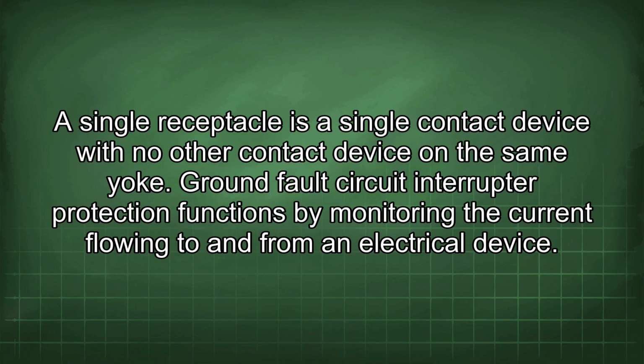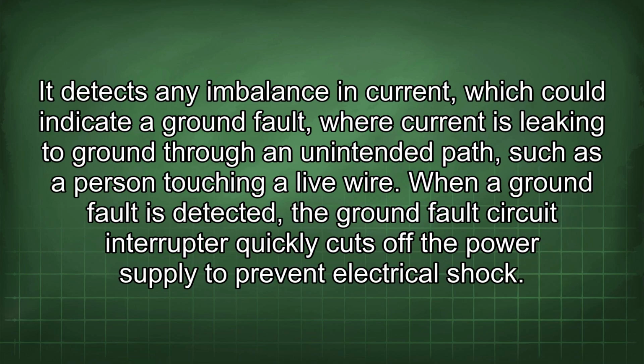Ground fault circuit interrupter protection functions by monitoring the current flowing to and from an electrical device. It detects any imbalance in current, which could indicate a ground fault, where current is leaking to ground through an unintended path, such as a person touching a live wire. When a ground fault is detected, the ground fault circuit interrupter quickly cuts off the power supply to prevent electrical shock.